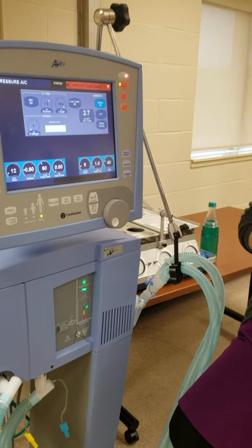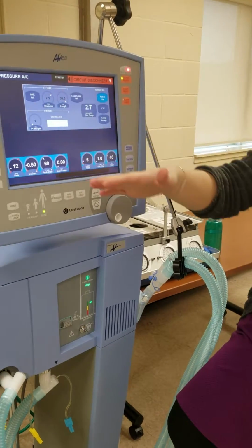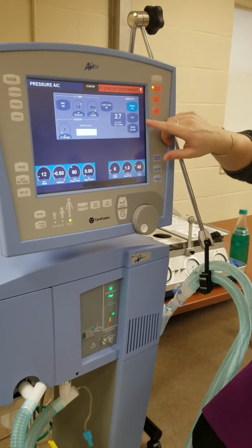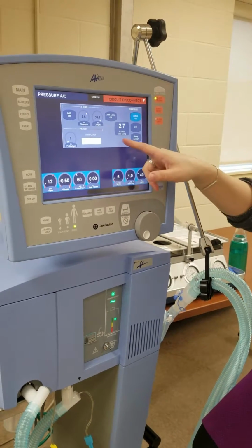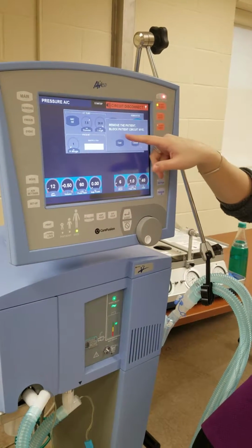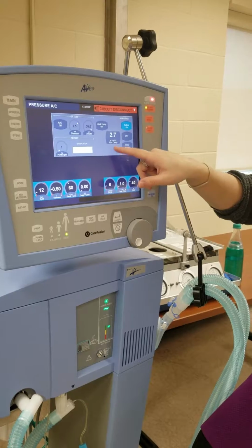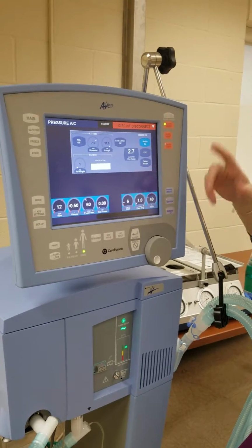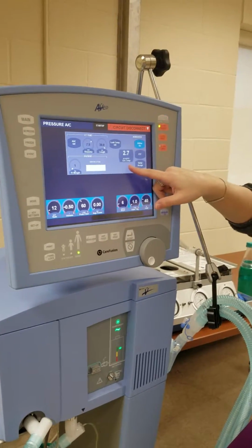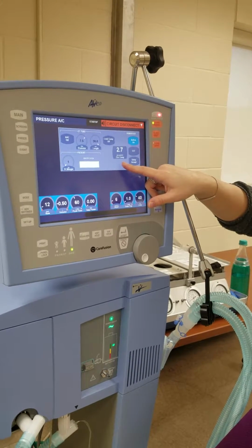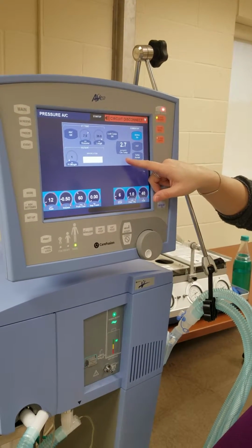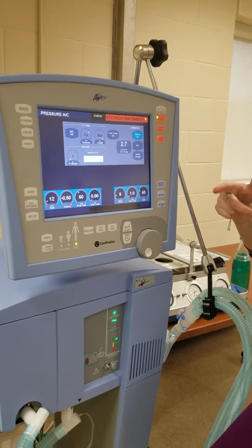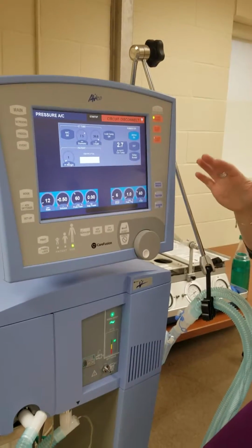You're more looking at overall volumes. Gotcha. So again, you probably won't use any of that stuff there. Typically, your normal day, you're just going to do that EST. The circuit compliance will actually display the number that it found when it did that test. So if you start the machine and it says 0 there, or it has stars there instead of numbers, you know that that circuit compliance test hasn't been done, and you need to do it before you hook it up to your patient. Still with me?